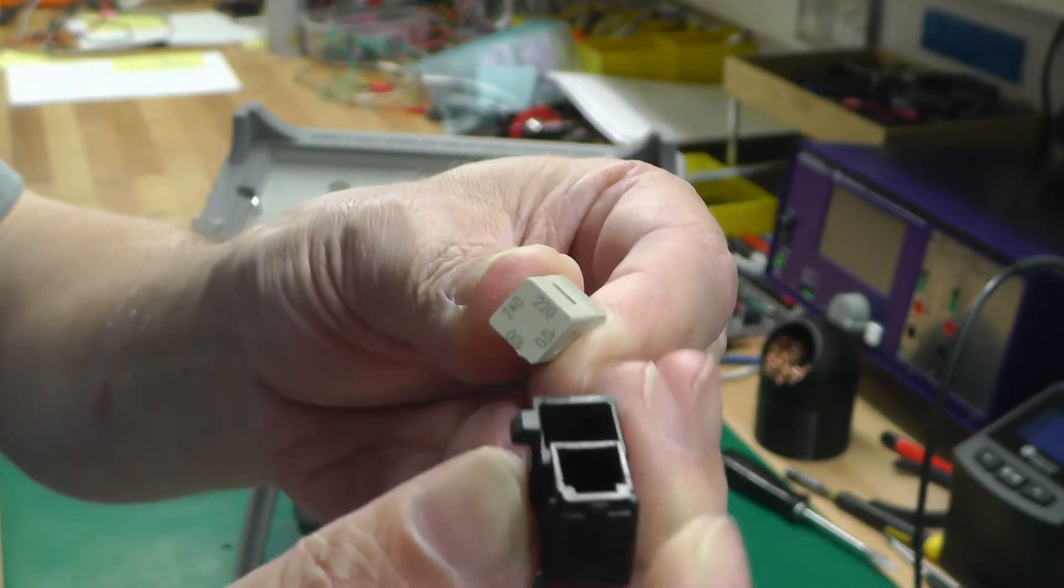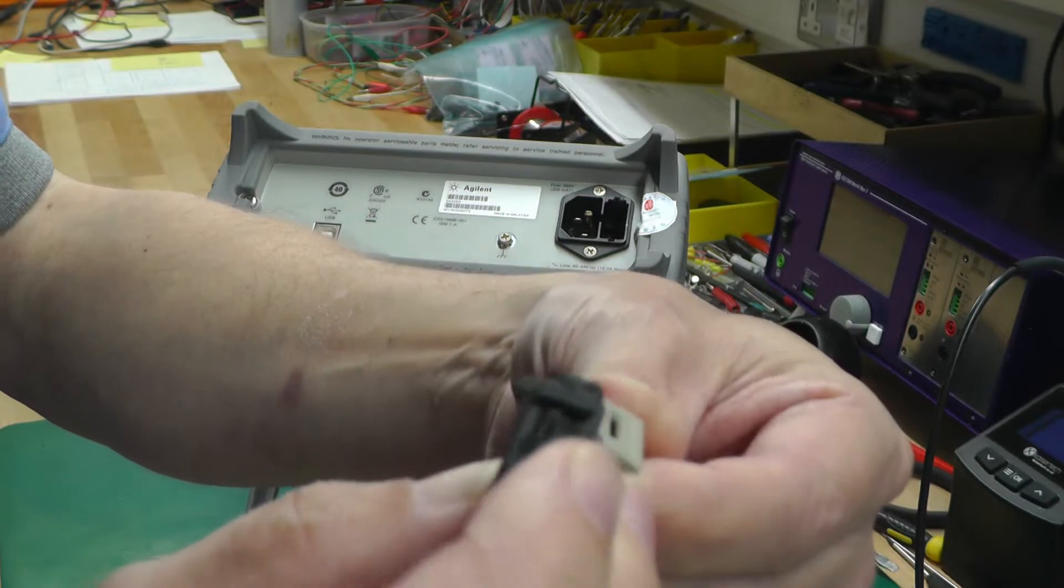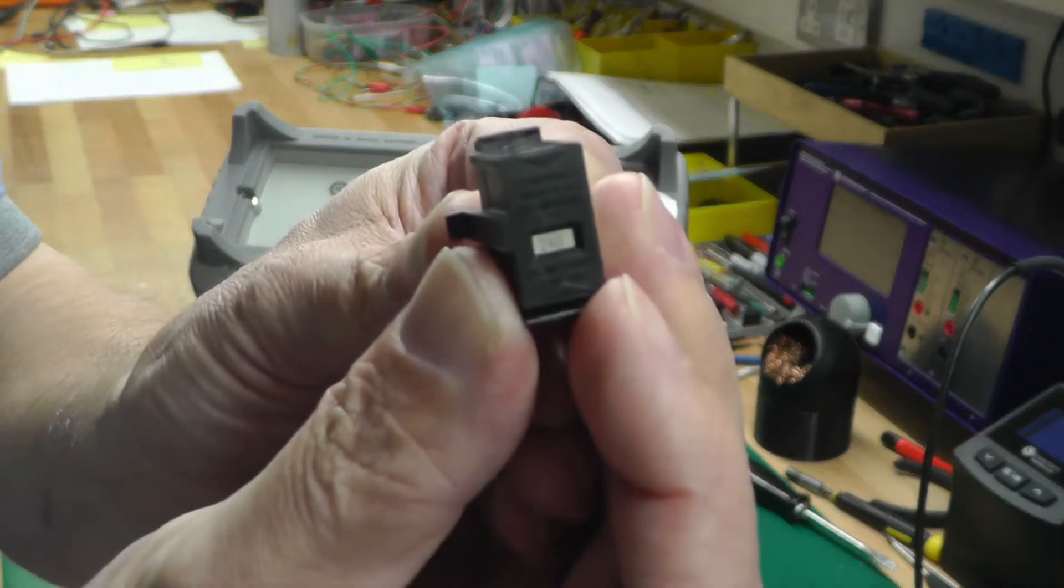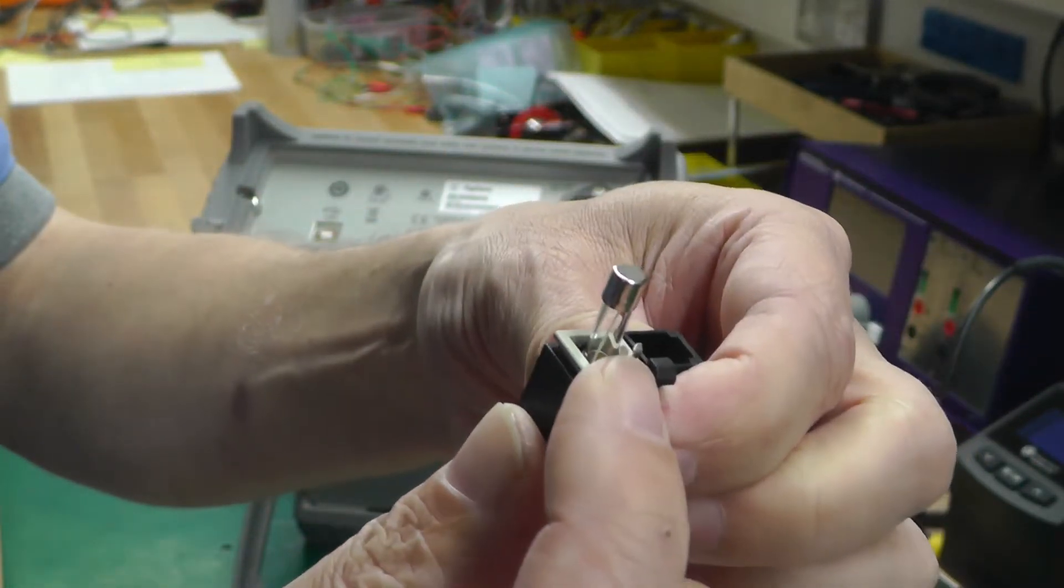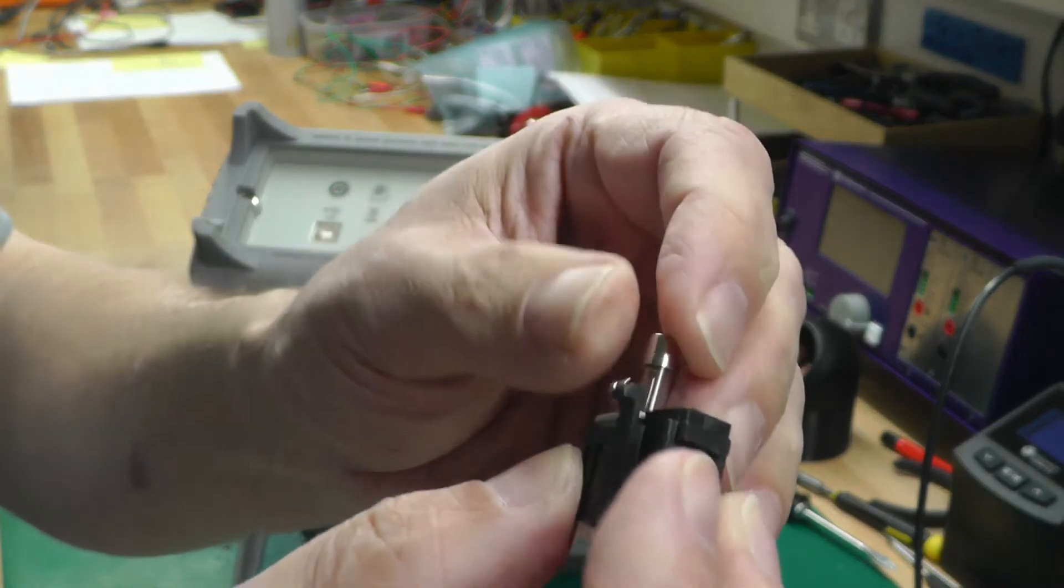You can see it's got the different voltages on it, and you just turn it around to the voltage you require. So I'll turn it around to 240. That's it set for 240 volts. Basically this contact here then goes into the receptacle down in the unit and makes contact for the 240 volt tap on the transformer.